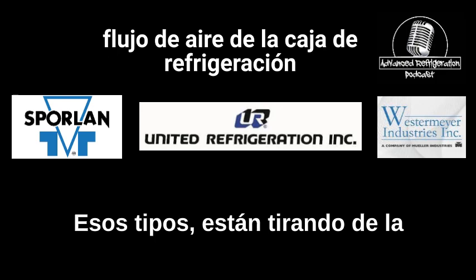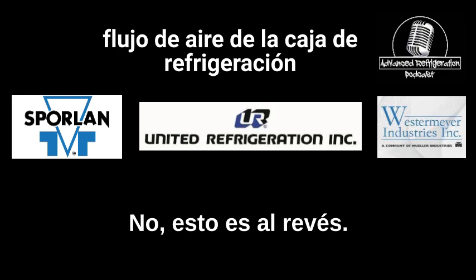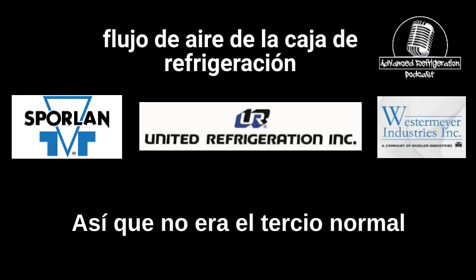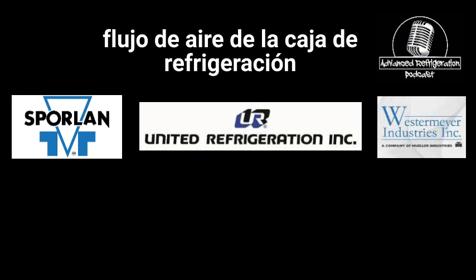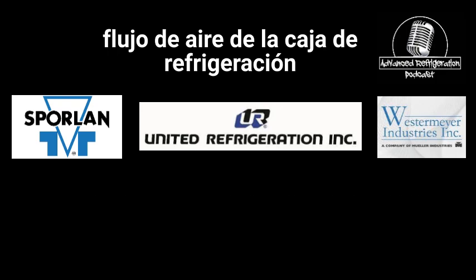You're pulling the air directly through there. Usually it would be going this way. No, this is reversed. Basically right where this is, the fan blade was as far away as humanly possible, so it wasn't the normal one-third or two-thirds of the way through the coil. It was just totally messing up the airflow. That looks like a pain in the ass to work on.